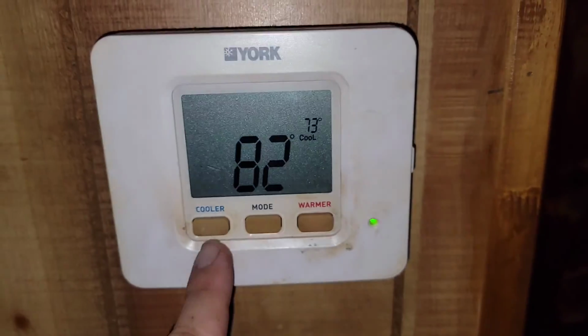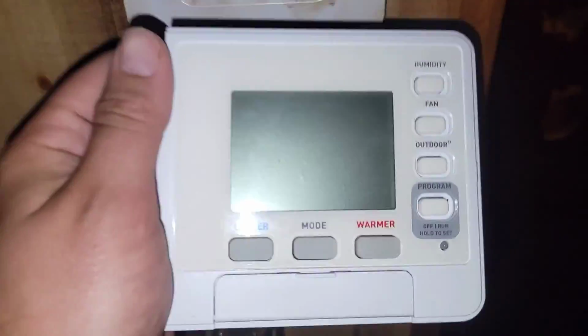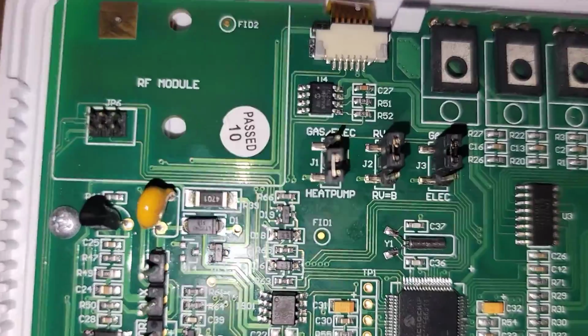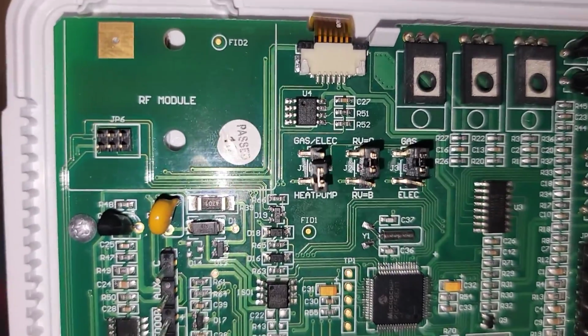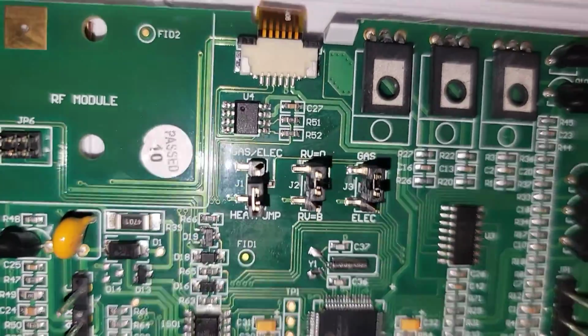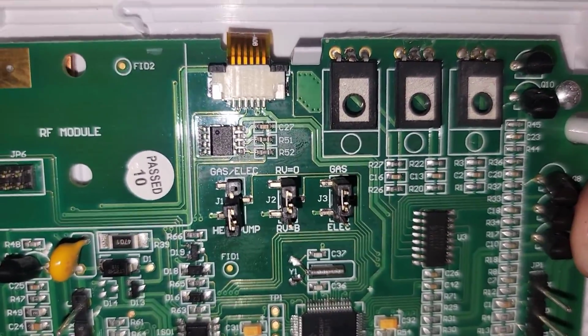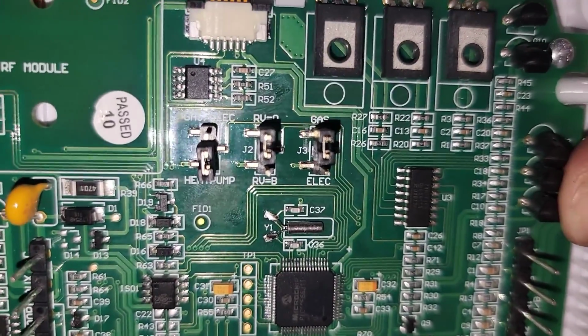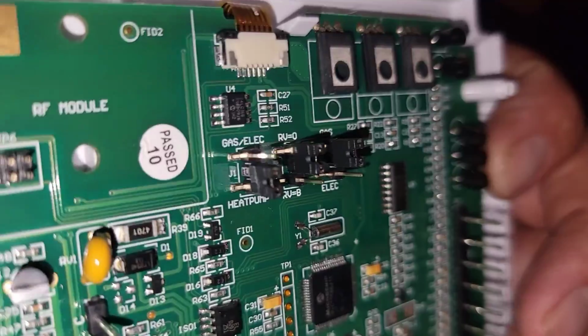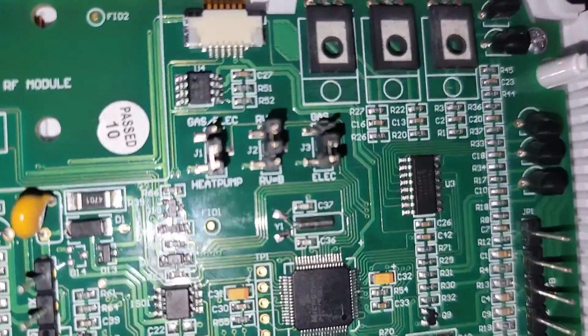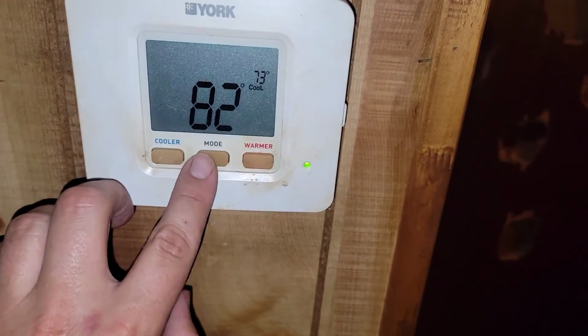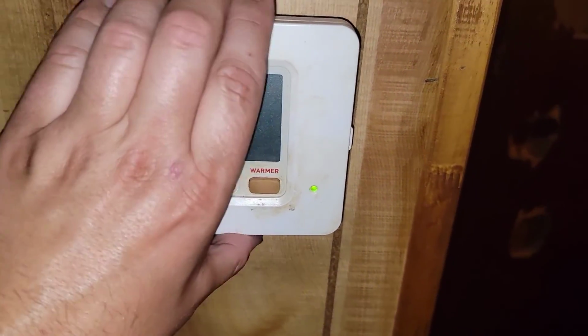So here's the thermostat. You can see it's been set to cooling. Here's the thermostat that's similar. Made sure that on the back it's set for heat pump instead of gas electric. It's set to energize in cooling, so it's set to O, reversing valve, and then also, oh, it's set to gas. I need to change that pin to electric. So I switched that pin to electric, and now I'm going to turn the unit off and pull this off the wall.